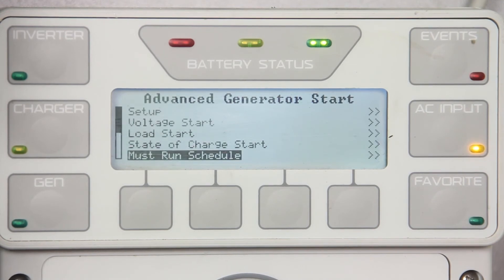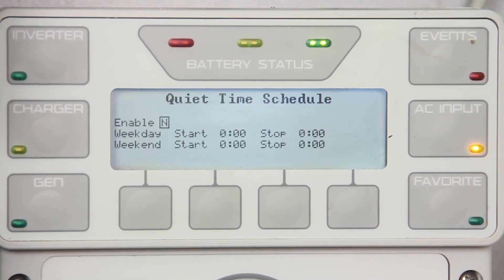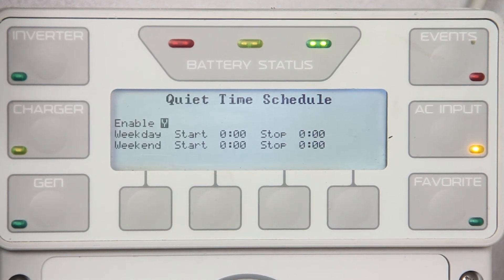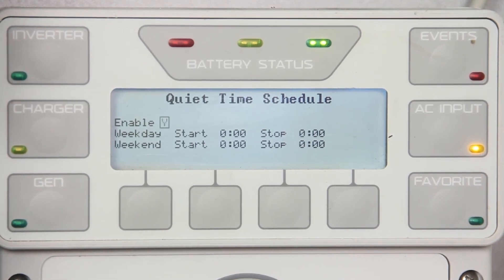Press up once and scroll down to quiet time schedule. This is a time period when the generator should not run. The 2 minute voltage start is considered to be an emergency start, therefore it will override quiet time. To enable, change the N to Y and enter the desired start/stop times.